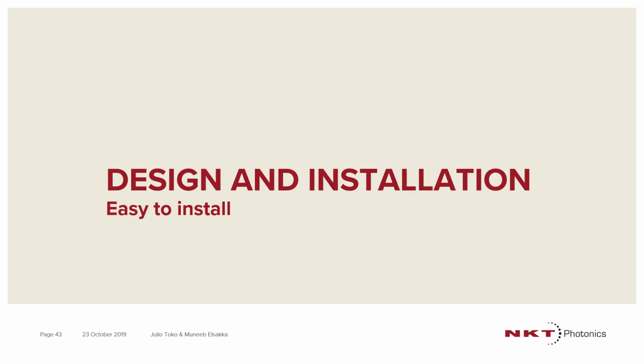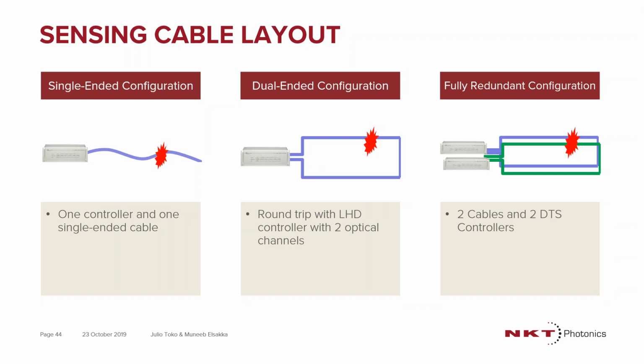Next, we'll be just touching upon the design and installation of the system. And it's a fairly easy install when you're talking about fiber optic linear heat detection. So just to go over the sensing cable layout, you have really three major ways to lay out a system. Just simple diagrams showing a single-ended configuration, double-ended, and then a fully redundant configuration.